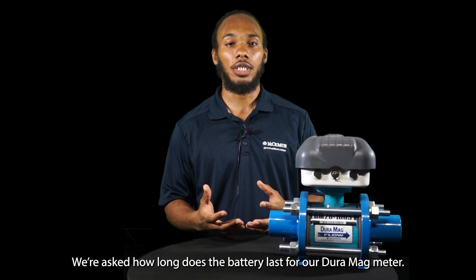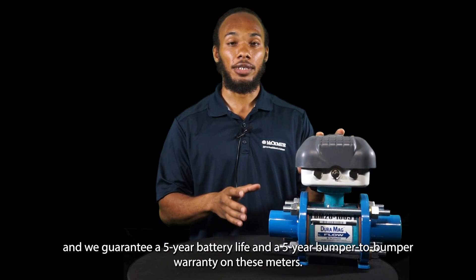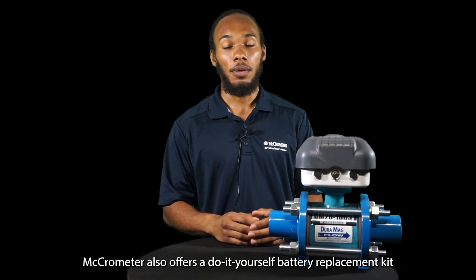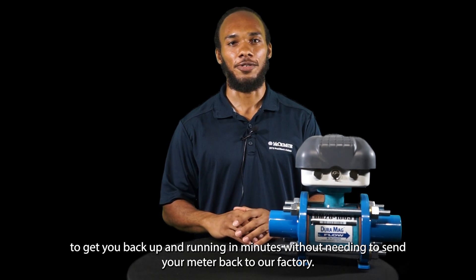We were asked how long the battery lasts for our Duramag meter. The converter for the Duramag is also used on the MCMAG 3000, and we guarantee a five-year battery life and a five-year bumper-to-bumper warranty on these meters. McCrometer also offers a do-it-yourself battery replacement kit to get you back up and running in minutes without needing to send your meter back to our factory.